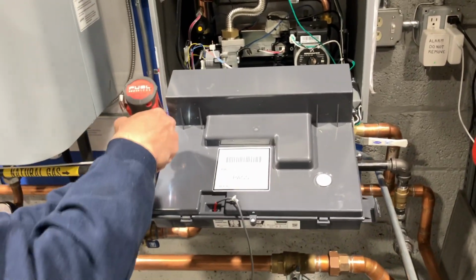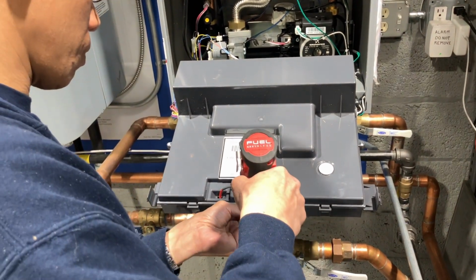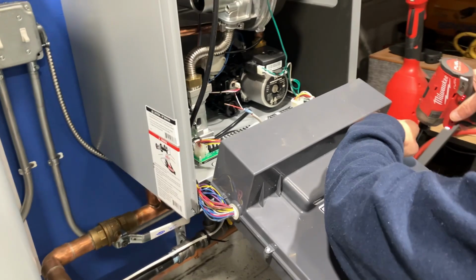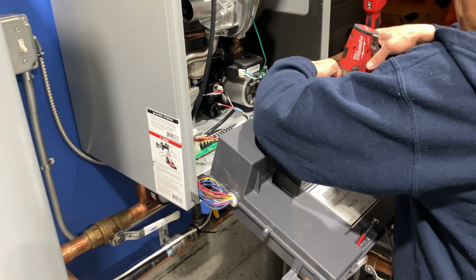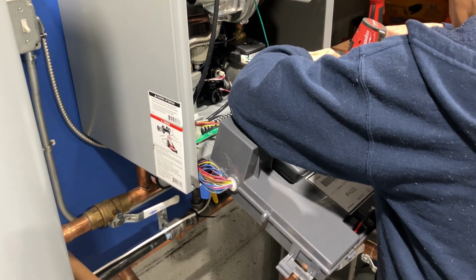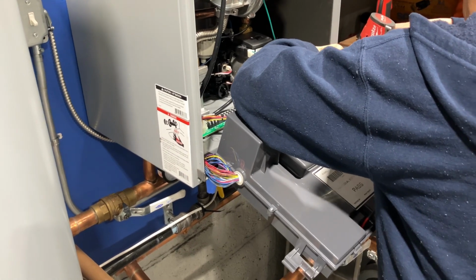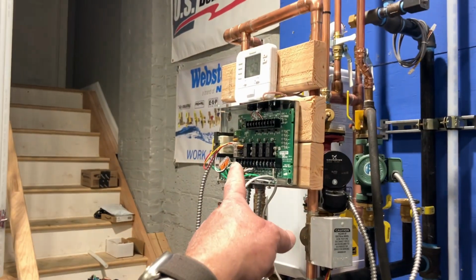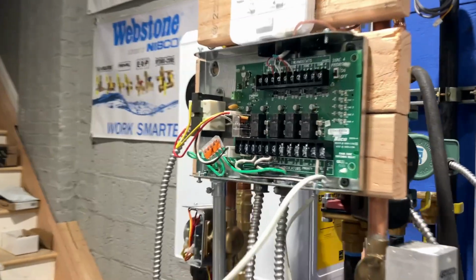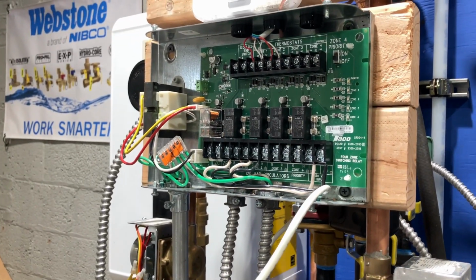So now we're going to be troubleshooting two problems. The dead boiler, which is not giving us voltage between R and W, so we can't interpret a heating call, and a dead Taco SR504 switching relay.